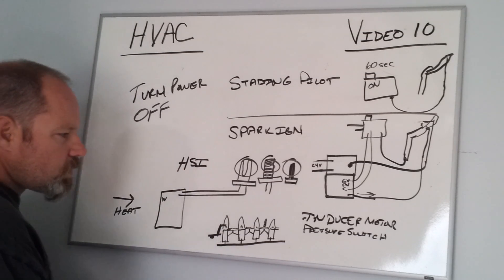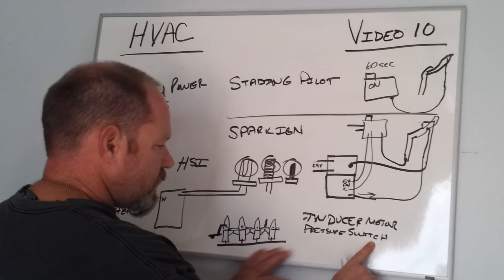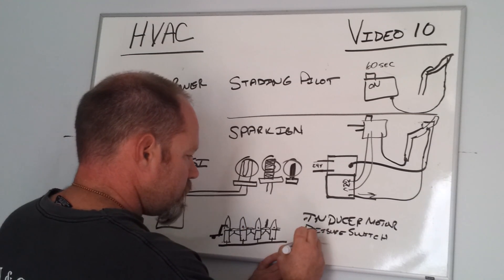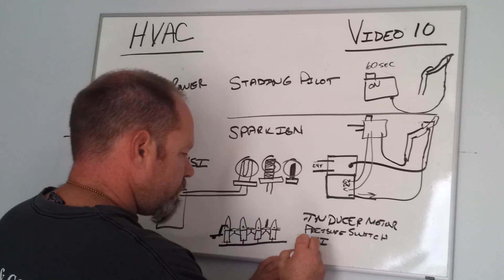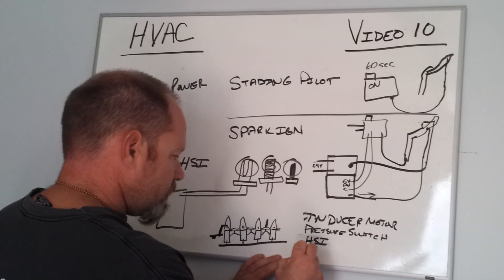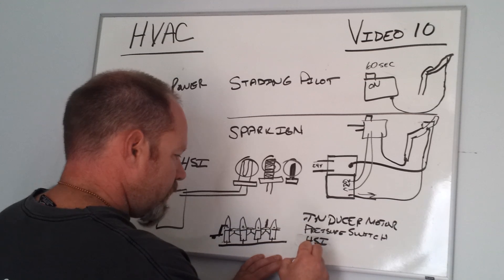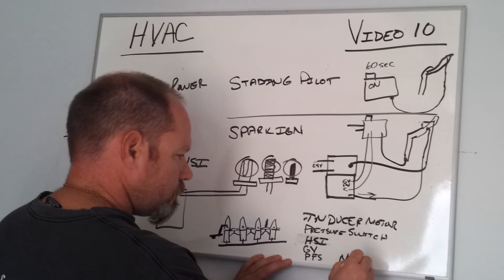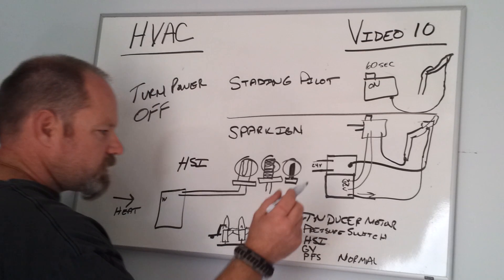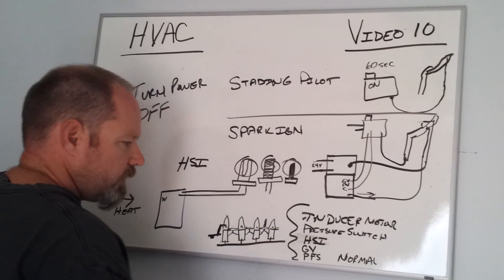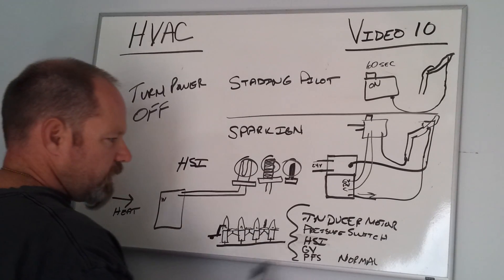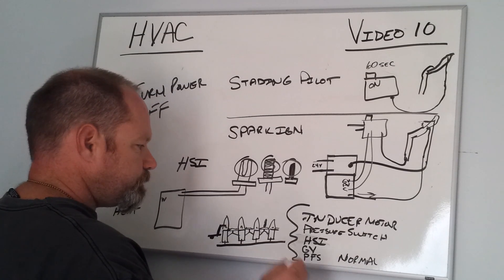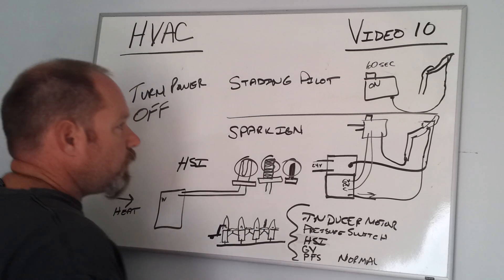So to summarize the sequence: pressure switch kicks in, HSI igniter glows, gas valve opens, pilot or flame sensor confirms flame, then normal operation. If you know the sequence of operation, that helps you determine what the problem is. If any one of these steps doesn't happen, you know that's where the problem is and the rest of it is fine.